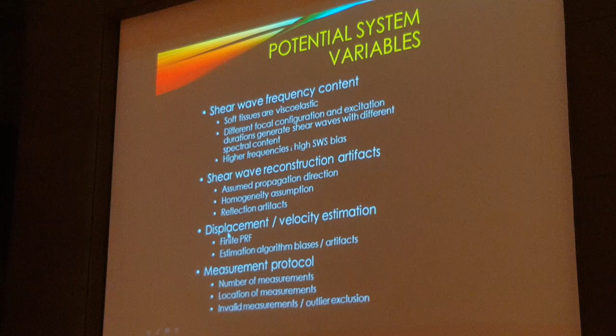And again, I look at this as the RF pulse strength is what's really critical, because the stronger the RF pulse, the stronger the shear waves, the easier it is for us to measure them. So again, we have attenuation problems. If you have steatosis or a cirrhotic liver, this is going to attenuate the RF pulse more. So these are the patients that you're going to have a hard time getting good measurements in, because we just don't have enough energy to penetrate those very stiff livers. And those are the ones that are going to be very challenging to you.